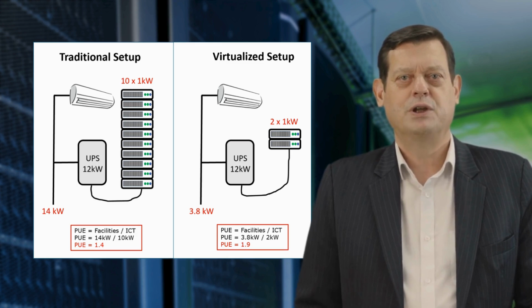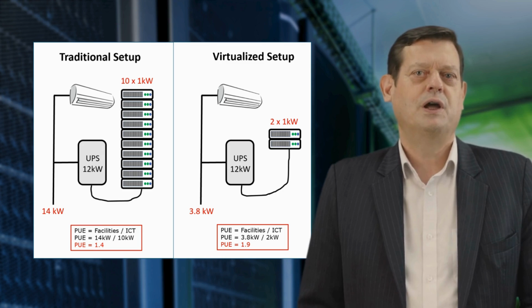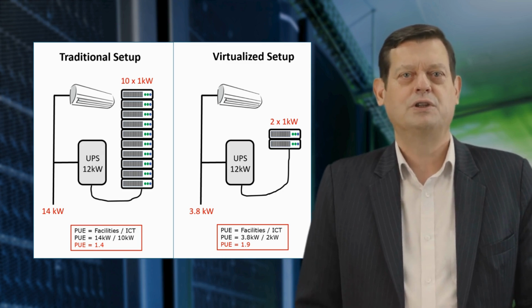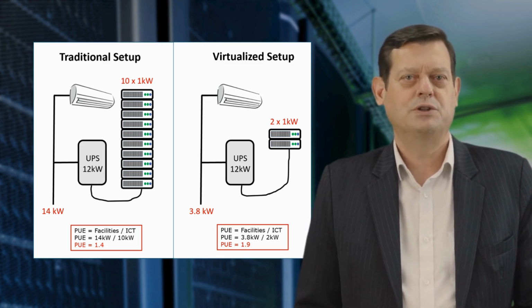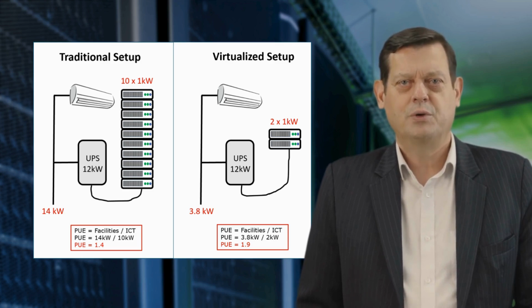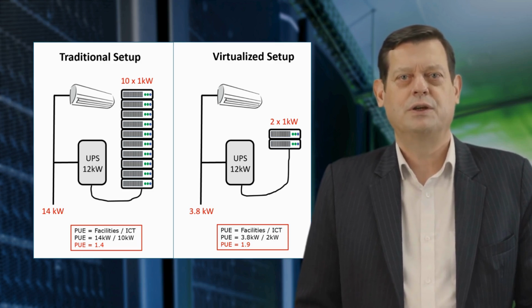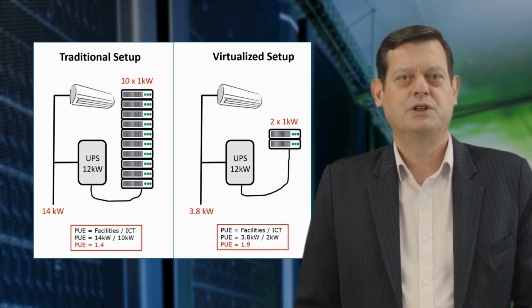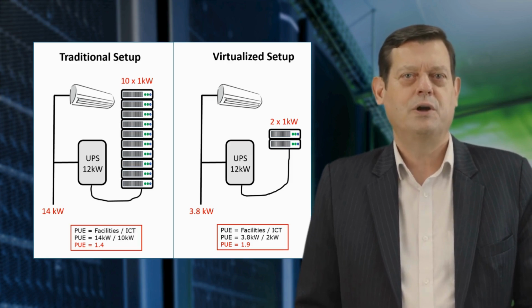Well, the UPS is still there. The air conditioning is still running, though far less active. The PUE is now 1.9, higher than the traditional setup, because the IT load has decreased but the supporting infrastructure remains unchanged. PUE now tells us we're inefficient, when in reality we've just made a massive improvement in IT efficiency and reduced our overall power consumption.